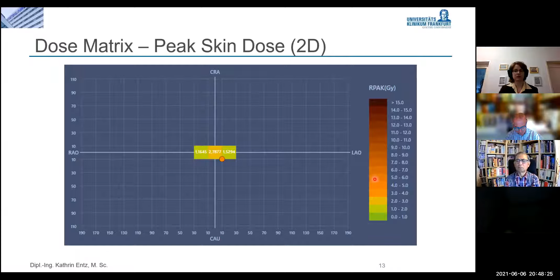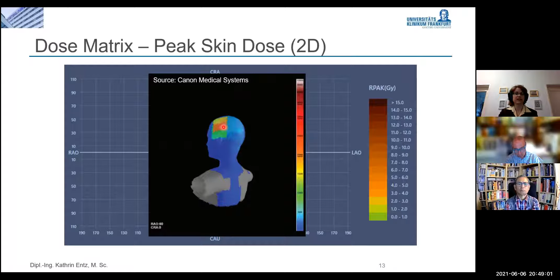You might also be familiar with an image like this. Some systems also display the peak skin dose on a phantom. They map those color-coded dose distributions on this phantom, so it is easier to see where the patient was actually exposed. And you can see here, from the perfectly square shape, that it was a radiological intervention to the head, and that in this area the dose was highest, and you have the level red, which means the doses were pretty high.